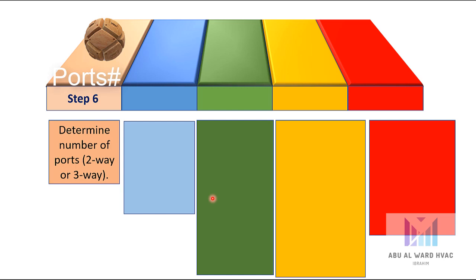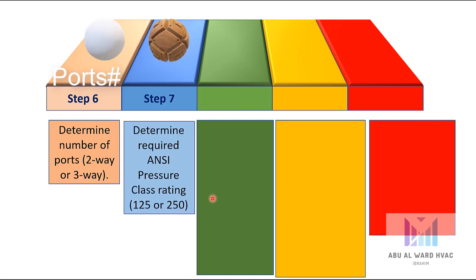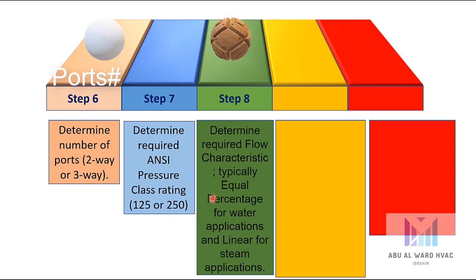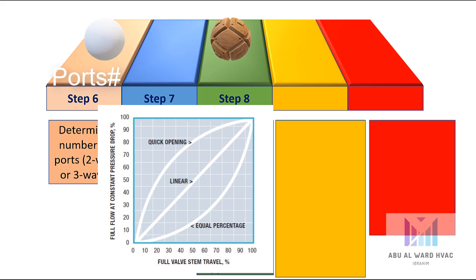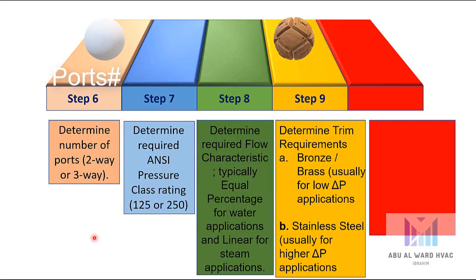Step 6: Determine number of ports — two-way or three-way valve. Step 7: Determine required ANSI Pressure Class rating, 125 or 250. Step 8: Determine required flow characteristic — typically equal percentage for water applications and linear for steam applications. Step 9: Determine trim requirement — bronze or brass, usually for low ΔP applications, or stainless steel, usually for higher ΔP applications.